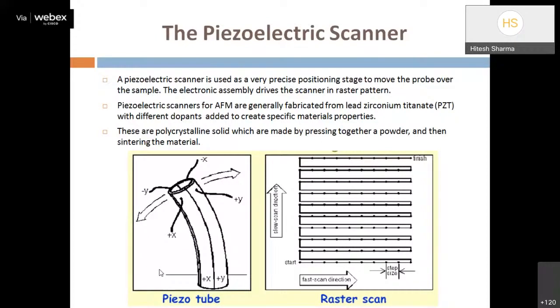The length, diameter, and strain coefficient of the PZT tube define the resolution of the whole AFM system. As more dipole movements are present within the scanner, higher resolution is achievable. If dipole moment diminishes, resolution also diminishes. If dipoles are not aligned, the scanner has almost no ability to move and has very poor resolution.